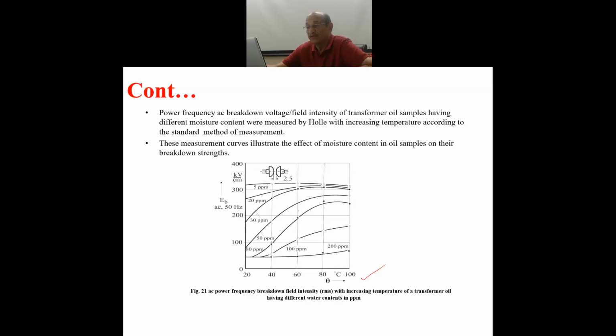because the humidity content in oil affects the breakdown strength very severely. Just to give you an idea, when the humidity content is only, in the topmost curve, of the order of 5 ppm, that is 5 parts per million, and you measure at, say, a normal temperature of 30 degrees centigrade, you are measuring, can you imagine, more than 300 kV per centimeter. This is the practical strength, as I was mentioning, of the order of 350 kV per centimeter.